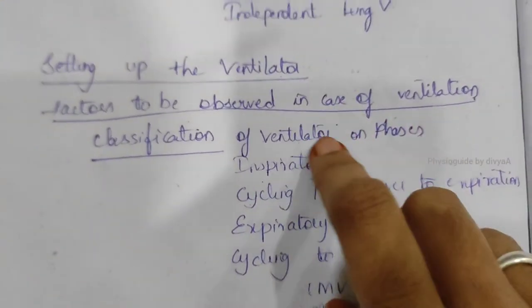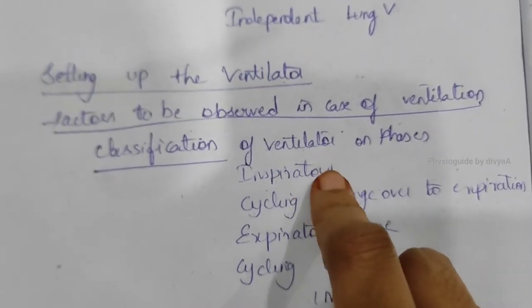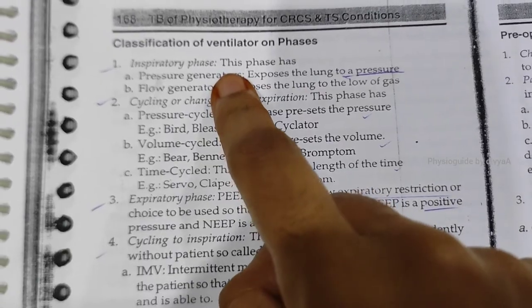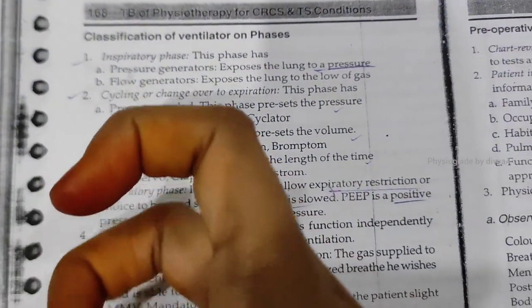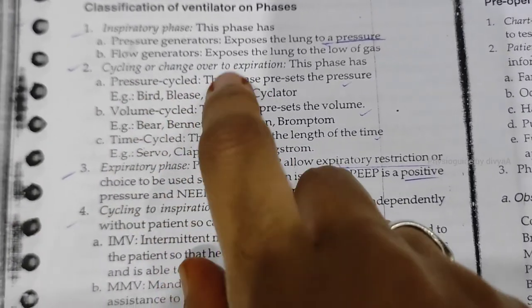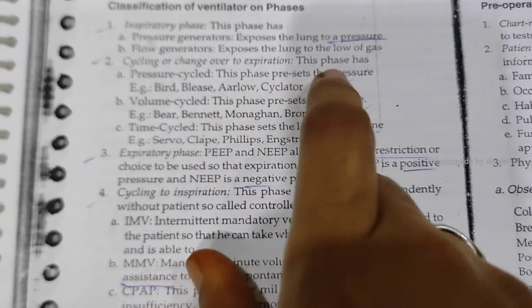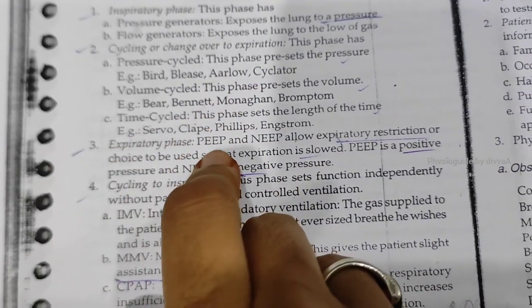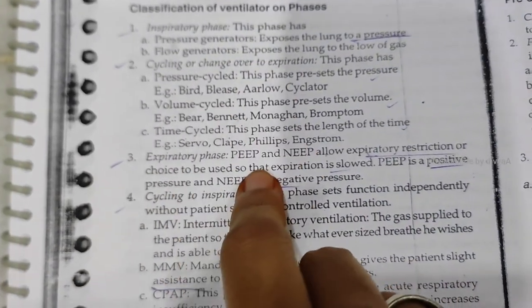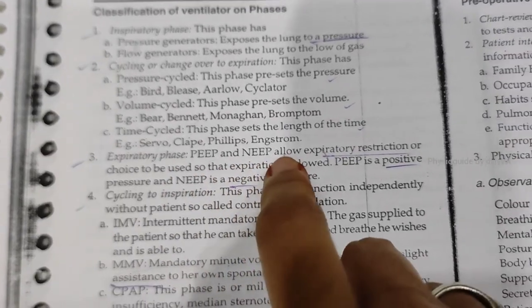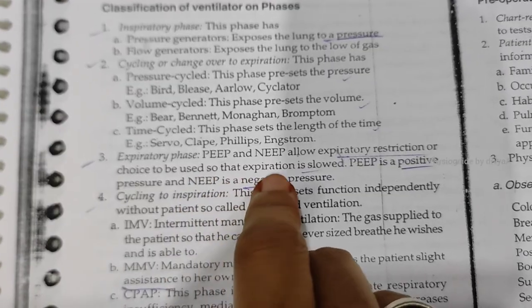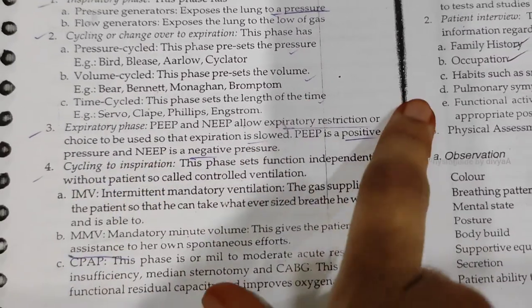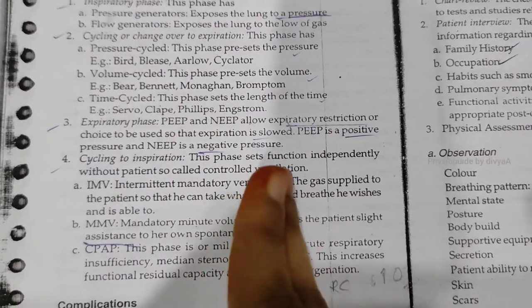Classification of ventilator by phases. Inspiratory phase: includes pressure generators, which expose the lung to a set pressure, and flow generators, which expose the lungs to a flow of gas. Cycling or changeover phase: the changeover from inspiration to expiration can be pressure-cycled, volume-cycled, or time-cycled. Expiratory phase: PEEP (positive end-expiratory pressure) and NEEP (negative end-expiratory pressure) allow expiratory restrictions, making expiration slow.